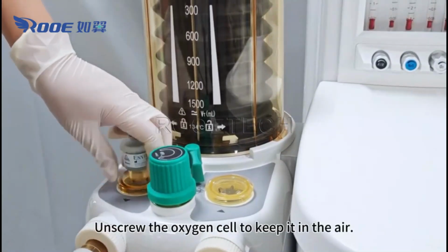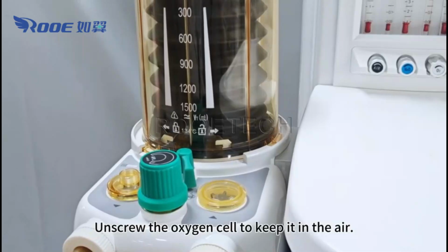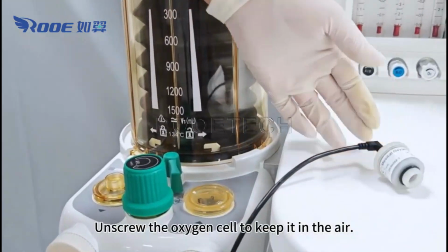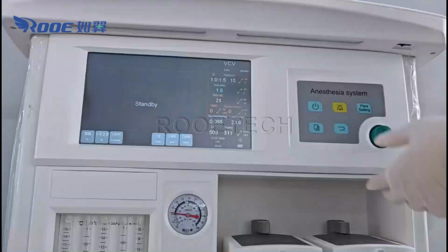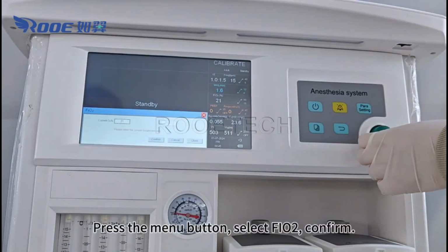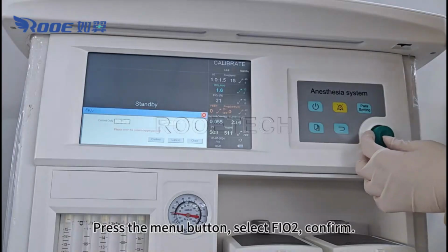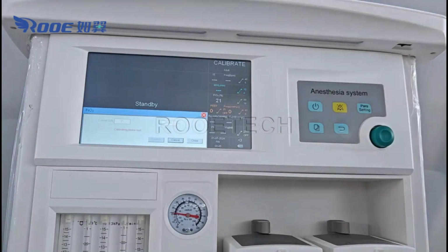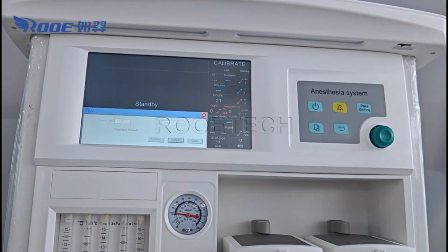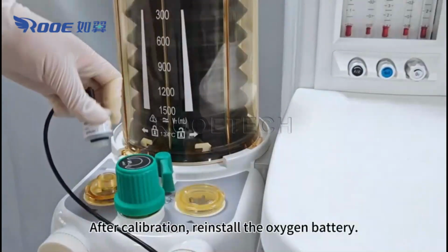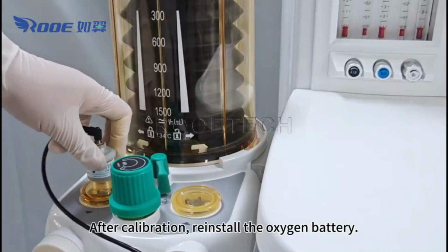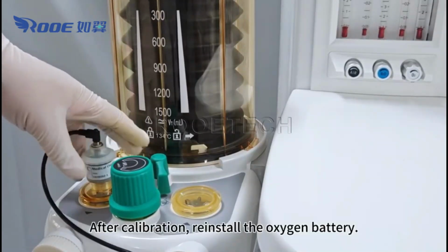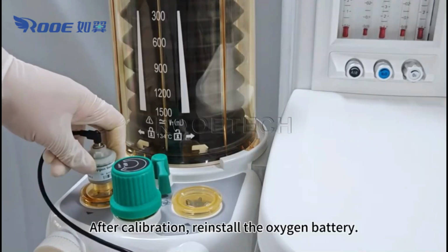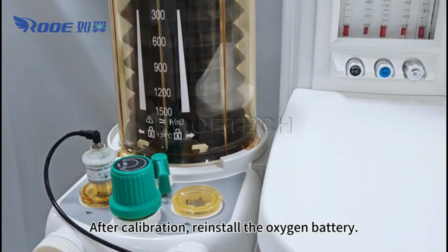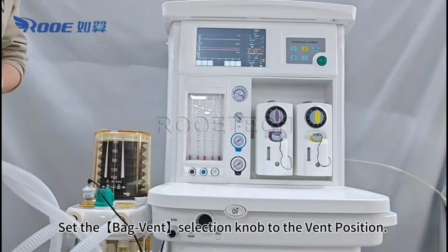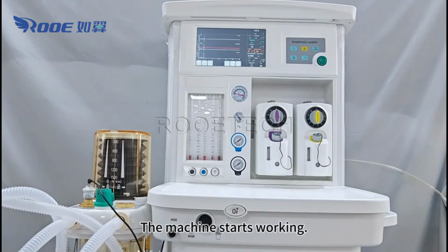Unscrew the oxygen cell to keep it in the air. Press the menu button, select FiO2, confirm. After calibration, reinstall the oxygen battery. Set the bag vent selection knob to the vent position. The machine starts working.